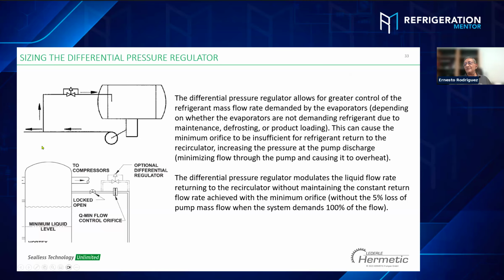At some point, three tunnels are stopped. You have 25 gallons per minute. The orifice can only handle a maximum capacity. It has limits because it's an orifice. But when you have an increase of pressure, this regulator is going to open. It's not a relief regulator. It's a differential pressure regulator.